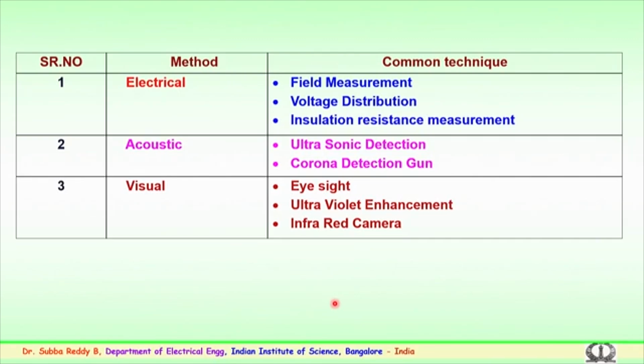There are methods used like ultrasonic detection or a corona detection gun. These again come under the classification of acoustic methods, where a pulse or ultrasonic methods are being used. Visually, as mentioned, it could be from normal eyesight, where you can trace and find out whether the discs are faulty in the field, like previously, where we have seen for the case of a glass insulator, the fault of the insulator could be seen through a normal eye.